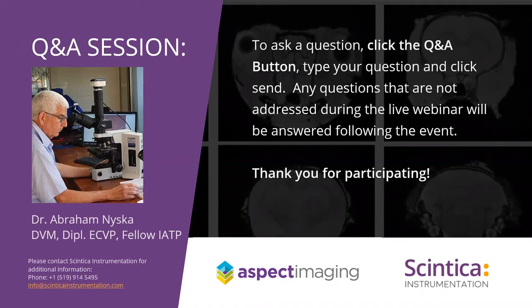Having a long scan time is less relevant for ex vivo work since the animal doesn't need to be maintained under isoflurane. For in vivo imaging you want to limit acquisition time, but with heating and physiological monitoring we know how the animal is doing. Ex vivo, with the automatic sample handling you can run multiple samples overnight without a technician present to interact with the system.